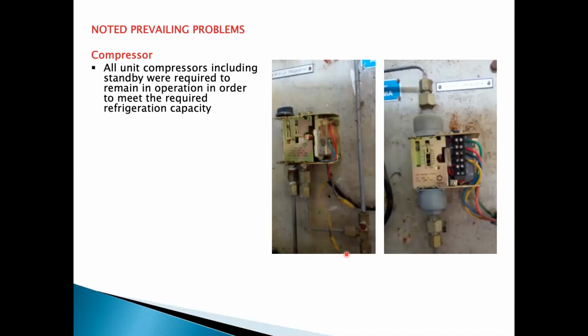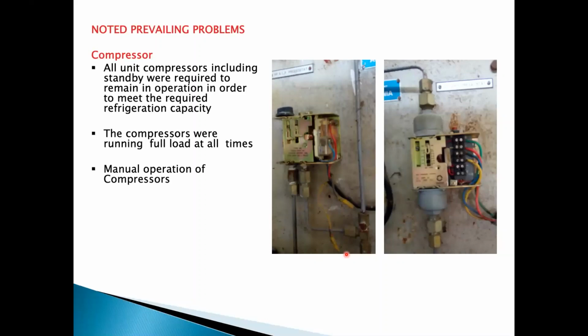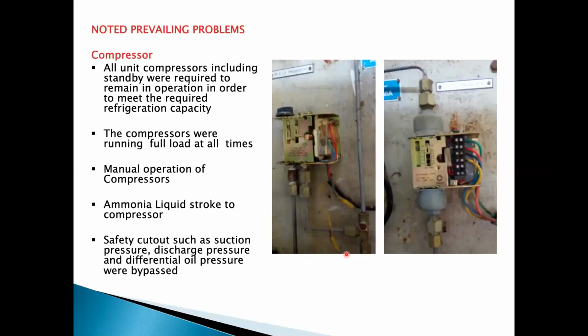On the compressor side, all the compressors, including the standby compressor, were running just to try to meet the capacity requirement, but they were still not able to achieve it. In fact, all the compressors were running on manual operation, not fully automatic. There was liquid coming to the compressor regularly and affecting the compressors. Please note, all compressors are gas compressors. The liquid cannot be compressed, so only gas must come into the compressor.